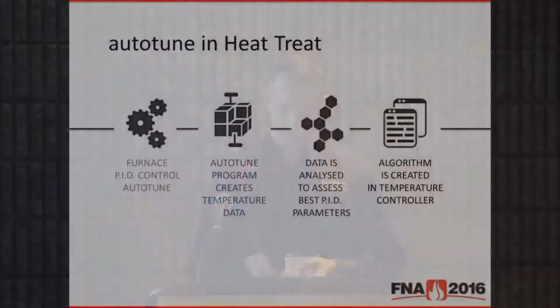So thankfully in more advanced controllers, you do have the ability to have what are called PID sets or gain scheduling. And so you can use a different set of PID for the low temperature, maybe the mid temperature, and the high temperature. We actually have some OEMs that just use our advanced controllers purely for a commissioning purpose, because they know it makes it much, much easier for them to commission the entire furnace by having that flexibility of PID sets.